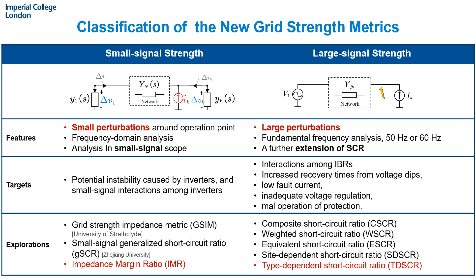For small signal strength, in our previous study, we used the impedance model to represent the dynamics of the entire network, and we call it a whole system impedance model or whole system admittance model. If we introduce small signal voltage perturbations at each bus and take the current response at the output, then from input to output we get a transfer function matrix, which we call the whole system admittance model of the entire network. It contains all the dynamics of the devices and of the system as well. If you pick out one of the diagonal elements of that matrix, you find that the equivalent circuit is essentially the same as how we define the traditional SCR.